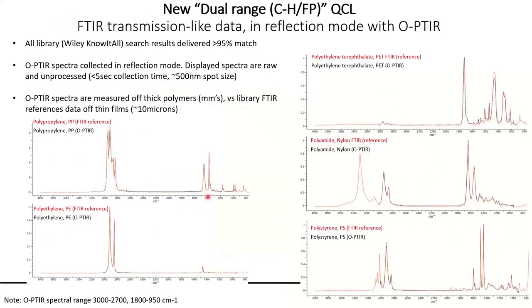To show how OPTIR spectra compare to reference FTIR, here is new data collected on a new QCL including the CH range together with the fingerprint. In red are FTIR reference spectra and in black are OPTIR spectra for five different polymers including polystyrene. The spectra are an almost perfect match — the FTIR collected from thin films in transmission, and OPTIR collected off thick blocks of the same polymer material in reflection mode.